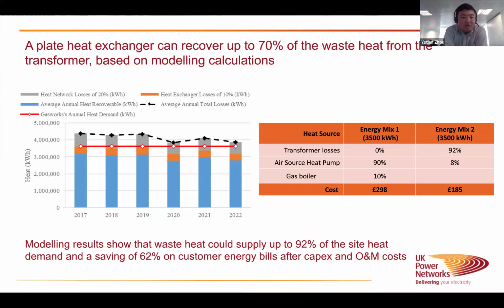In Discovery as well as in Alpha, we studied the amount of waste heat available from those power transformers within the substation. Those studies are based on 5 years of historical load data on the transformer, as well as the data sheets of those transformers to account for how much losses they would produce.